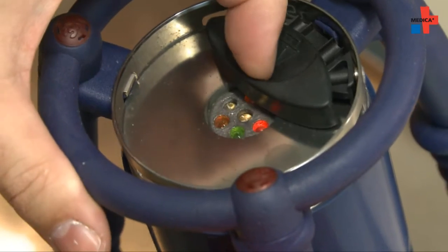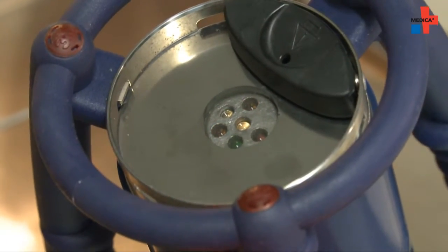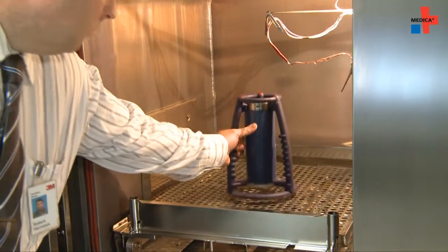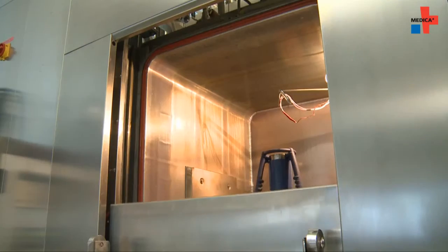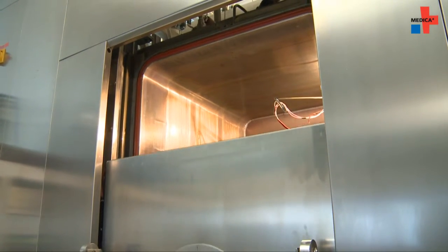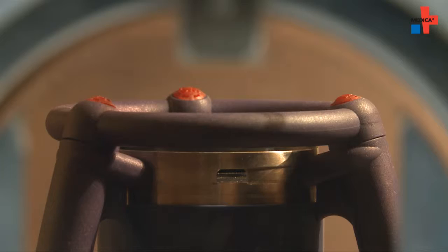They have to be checked every day before they are used. This checkup is made whilst activating the unit. The unit is placed in a sterilizer in an empty chamber. Here, a normal production process is started, whereby the sterilization time is limited to 3.5 minutes.